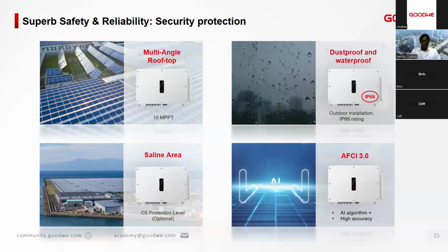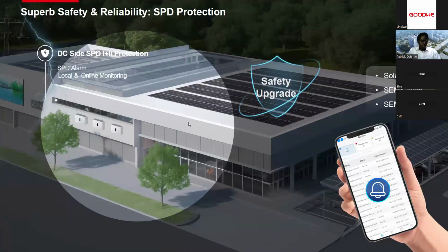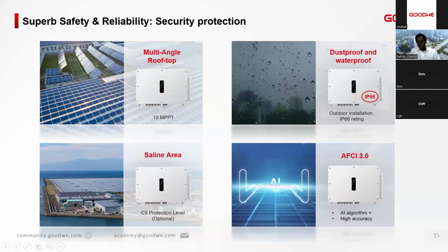Also, we offer great reliability. As you can see, we have 10 MPPTs. The advantage of this, of course, is that you are able to do different orientations without compromising on your production. Then the inverter is IP66. Therefore, it is dust-proof and waterproof, and it is able to withstand some harsh conditions. And you are also able to do outdoor protection. We do have an optional C5 protection level. Therefore, if you are installing in a seaside area, we are able to offer such a solution. The GT can also be integrated with the AFCI 3.0, which has a high AI algorithm and high accuracy to protect your inverter against any arc faults.